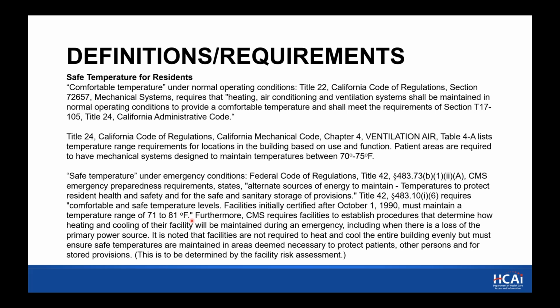Furthermore, CMS requires facilities to establish procedures that determine how heating and cooling of the facility will be maintained during an emergency, including where there is a loss of primary power source. It is noted that facilities are not required to heat and cool the entire building evenly, but must ensure safe temperatures are maintained in areas deemed necessary to protect patients, other persons, and for stored provisions. This is to be determined by the facility risk assessment that will be submitted with the assessment. So in other words, the entire facility doesn't need to be on emergency power for the cooling, but there needs to be provisions made for the location of patients or residents in a SNF to be in a safe condition during the power outage.